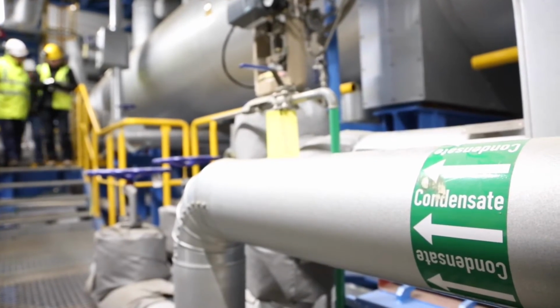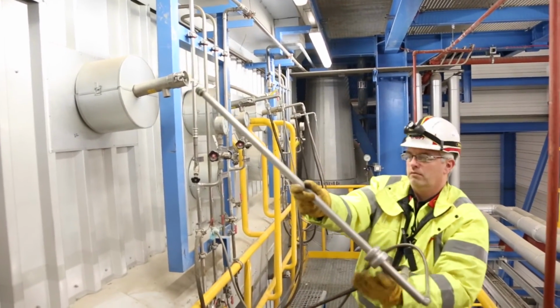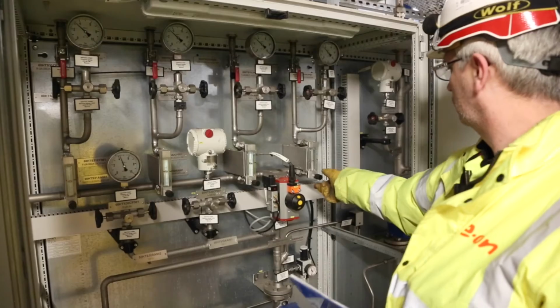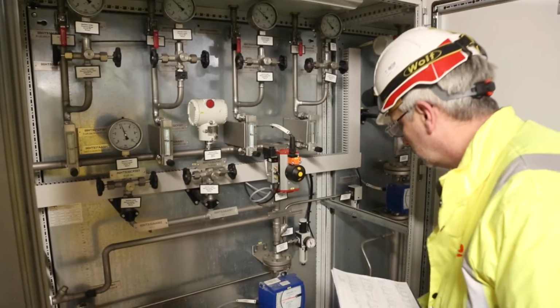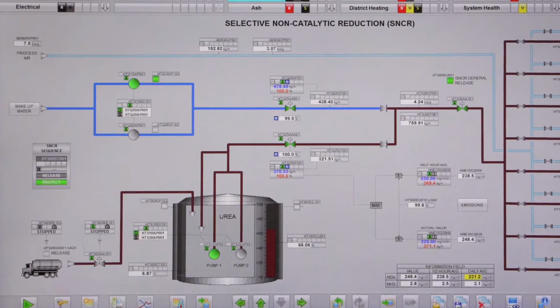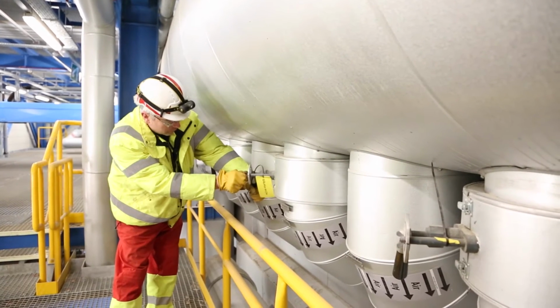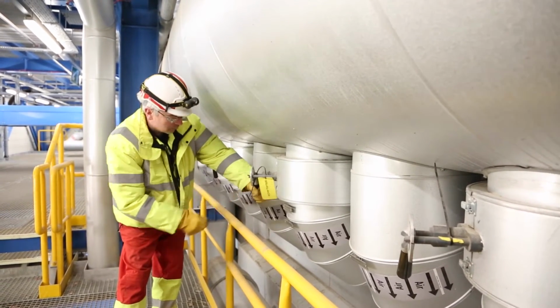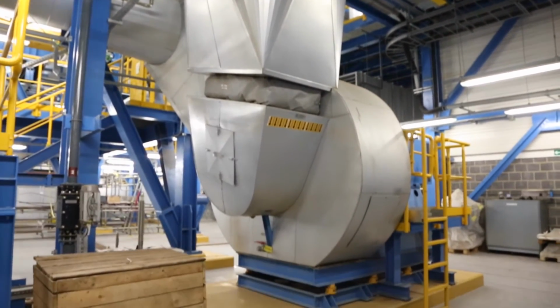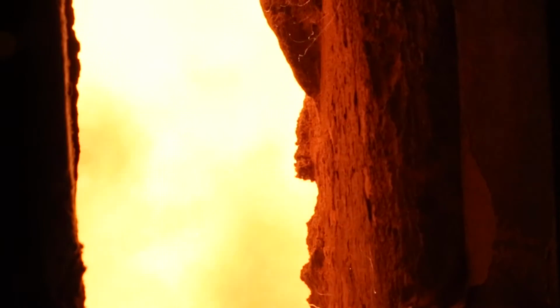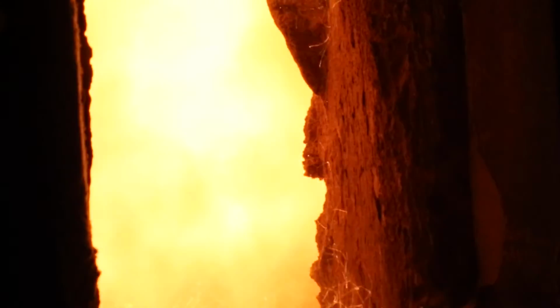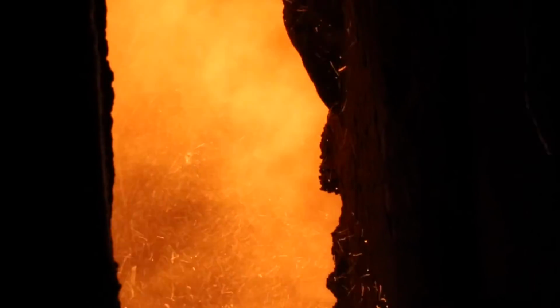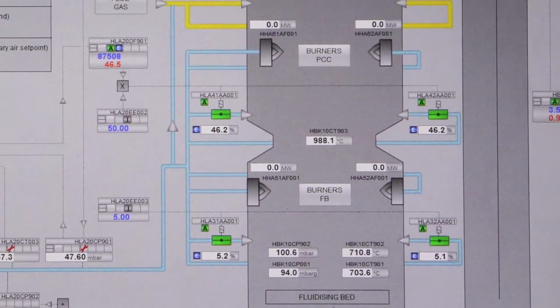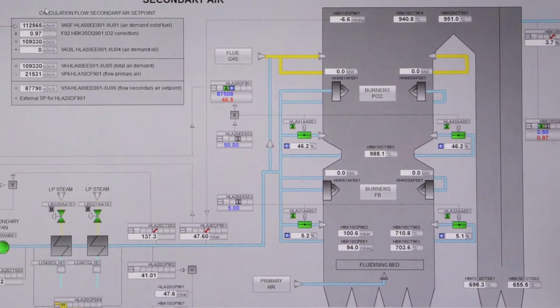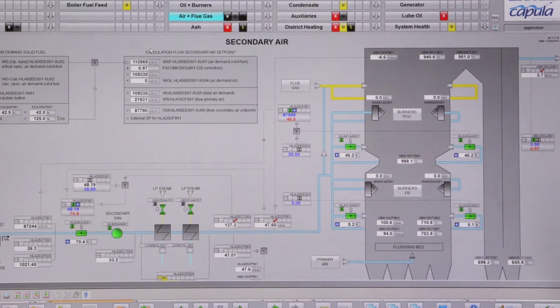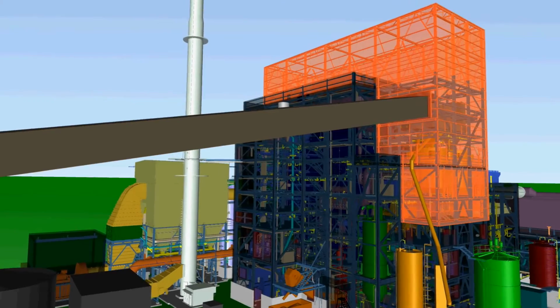A selective non-catalytic reduction system is installed in the post-combustion chamber. There, a water-urea mixture is injected into the flue gas, reducing the nitrogen oxide content. The staged combustion process itself is controlled in such a way by the combustion air distribution and the recirculated gas injection that no temperature peaks in the post-combustion chamber occur, which otherwise would increase the raw gas nitrogen oxide content. Any potential dioxin precursors are destroyed by maintaining a flue gas temperature above 850 degrees Celsius for more than 2 seconds, downstream of the injection of the secondary air.